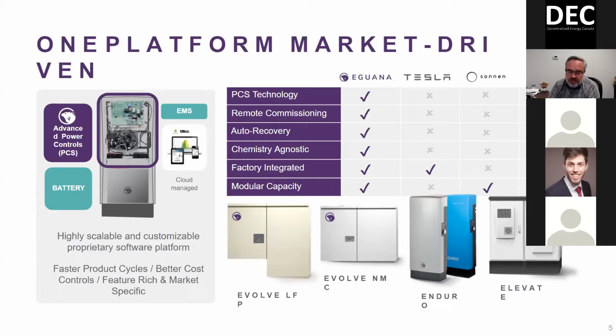The key part of this slide is the three components, which you've seen in the different project descriptions earlier today. There's the battery itself, where the energy is stored; the advanced power controls, where the action happens—charging and discharging the battery, maintaining grid stability, and meeting all the grid interactive requirements; and then the EMS is the third piece. The EMS is like the supervisory controller that decides when and how much to charge and discharge the battery, and potentially controls loads and other devices in the microgrid or local network.